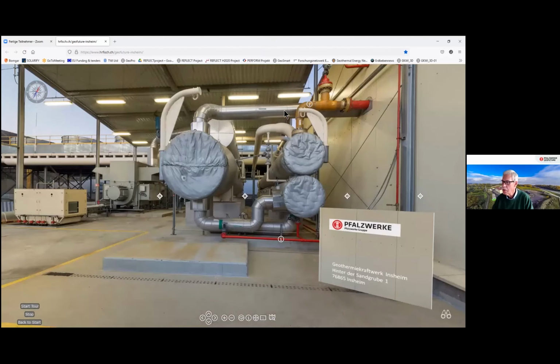This is the group of our heat exchanger. The hot brine is coming through this isolated pipe, entering our vaporizer on top. This is the hottest point of the heat exchanging system, and then flowing out of the heat exchanger through 2 preheaters, and then flowing back into the brine treatment facility and back to the reinjection well.